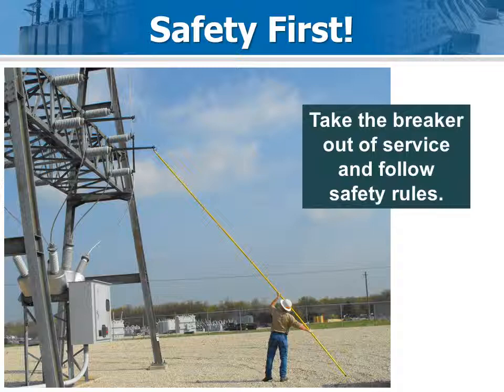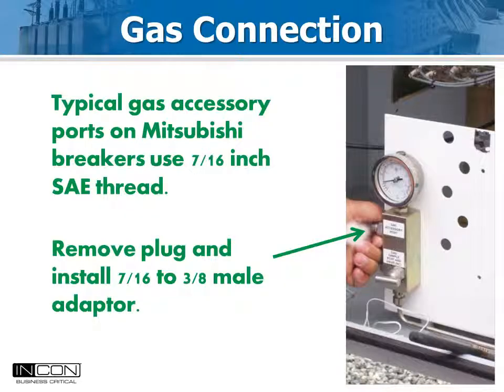Schedule the outage in advance so things go smoothly. If the crew shows up prepared with all the parts, installation generally takes less than 2 hours. Depending on the vintage and the model of the circuit breaker, specific gas connections vary. If you give Mitsubishi the breaker serial number, they can tell you exactly what the options and thread sizes are in advance. Usually the connections to the block are 7/16" SAE, requiring a neoprene O-ring and silicone sealant.